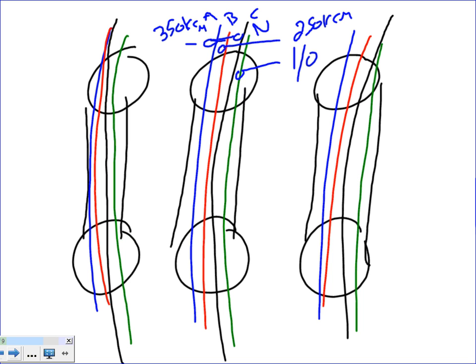If you decide to go that far out, again, there's nothing wrong, guys, with going 350. Don't misunderstand me. So it's under value engineering. I personally think going 350 on these runs, look at how much cover you're going to put. On these runs, value engineering, I would not hesitate putting my stamp on it. Why would you go to 250 when you'd never go on certain phases more than 250 amp? Why should you go 350? I mean, there's nothing wrong by design.